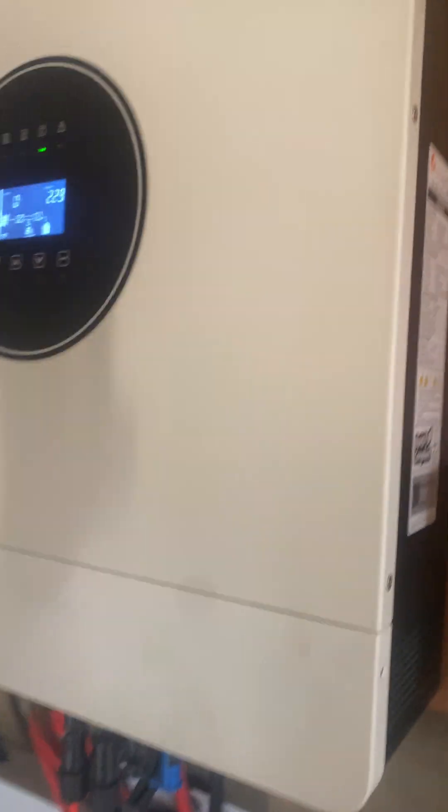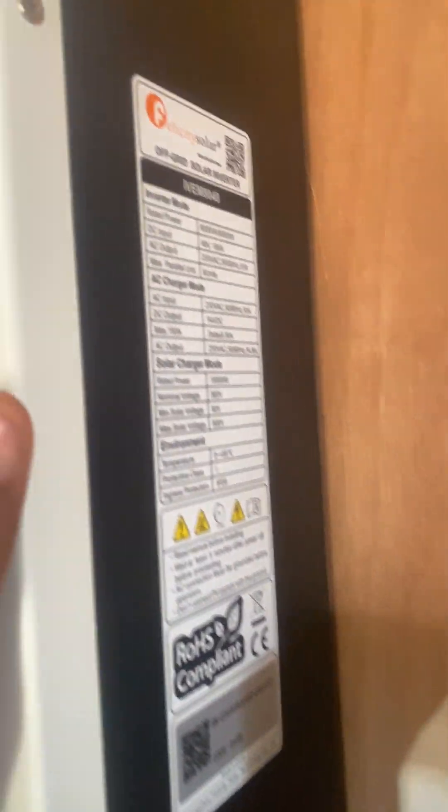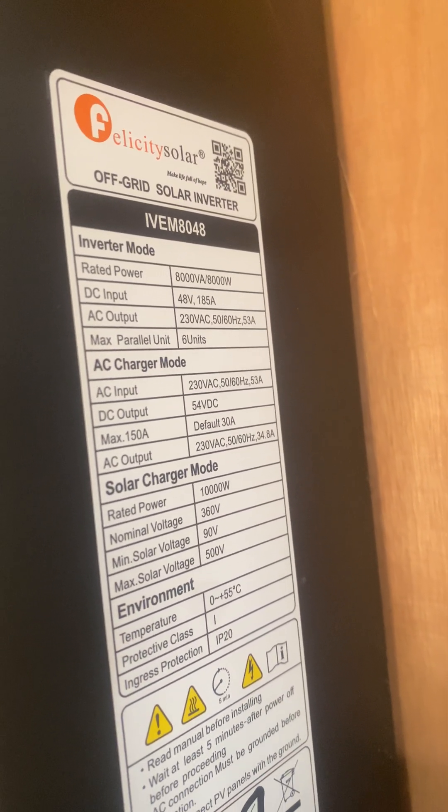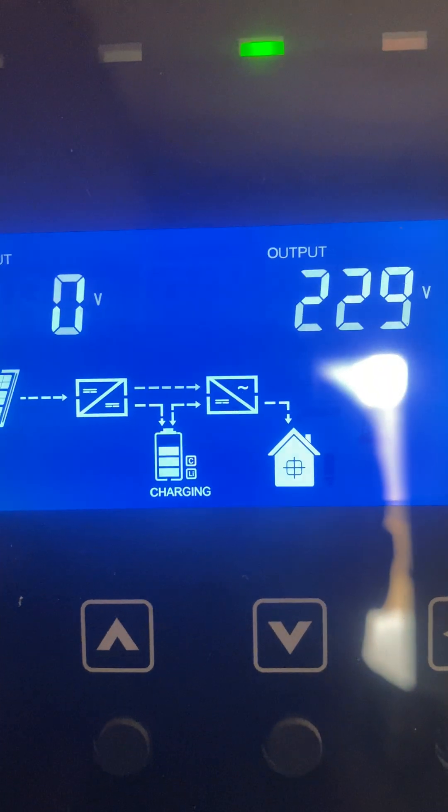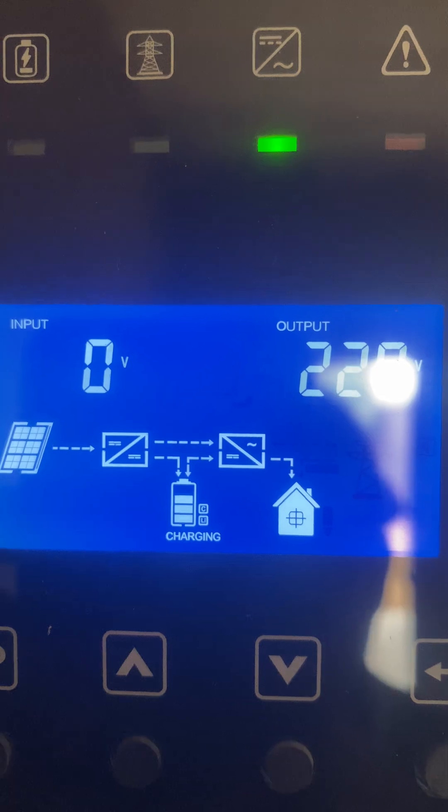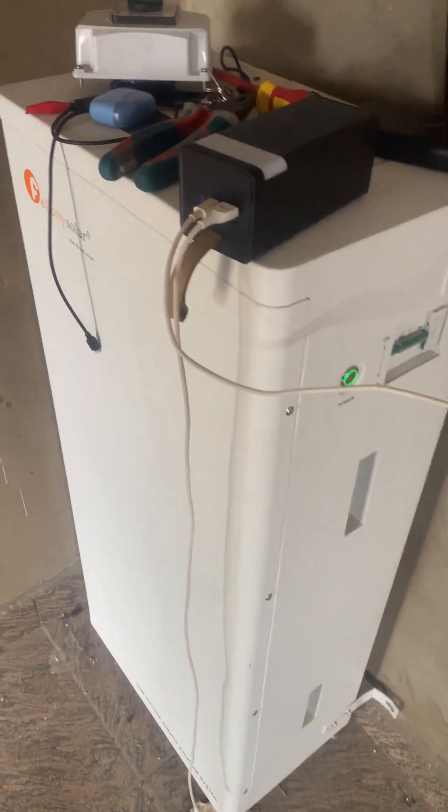Someone asked about setting the inverter to lithium when it's not selecting. We are using an IVEM 8kVA for this demonstration. As you can see, it is communicating and set to lithium. The wire is connected on the RS485 port, not on the CAN port. On the battery side we have the 15kW new series.